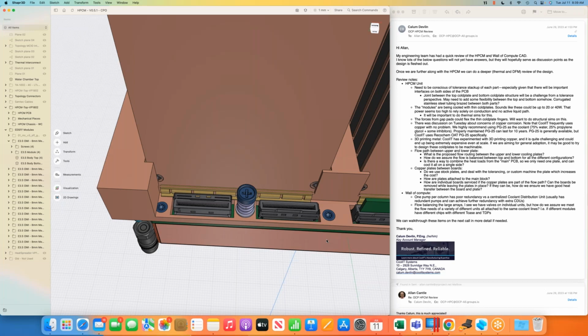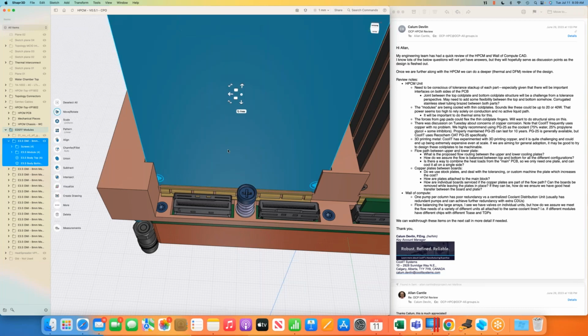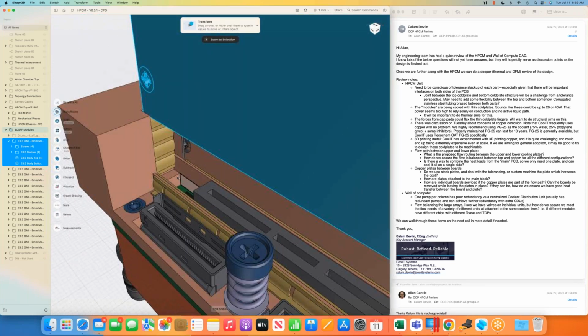Right. Because where I would also be concerned, Alan, is that connection point, depending on what that spring-loaded thing looks like. If it's something like this, where you actually have less surface area at the joint, like there are those gaps, you want as much contact area as possible. So I would just be a bit concerned about whether we can conduct all the way down to where we need.